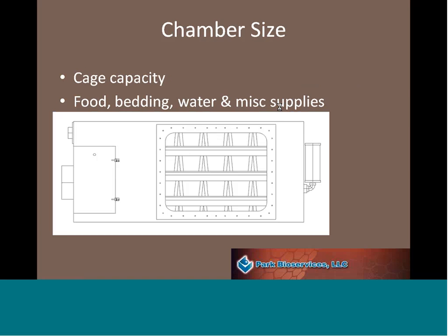So, chamber size. When I originally started in isolators, I came from a large breeding company, and we had a particular size in mind that we felt was ideal. What I found over my 16 years of experience with isolators is that it really was only ideal for them and not for the rest of the community. So in looking at the chamber size, you have to consider a number of different things. How many animals do you want to work with at that ideal size? But also being able to house all the food, bedding, water, and miscellaneous supplies that you're going to need for the duration of the study.